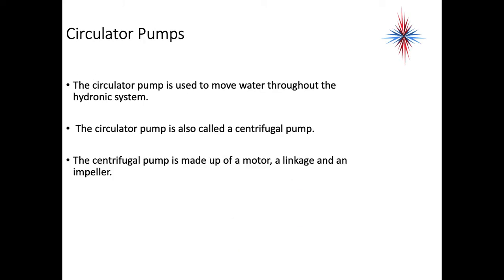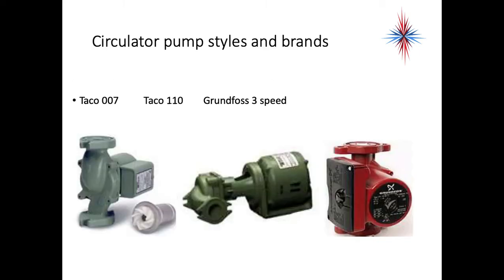The circulator pump is found on most systems and is used to move water through the hydronic system. It's also called a centrifugal pump and is made up of a motor, a linkage, and an impeller. There are several styles and brands — the Taco 007, the Taco 110, and the Grundfos three-speed pumps are the most frequently found, with the Taco 007 still being the primary one seen in most residential applications.